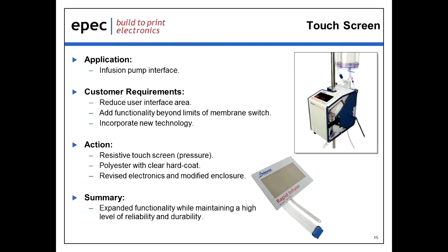The first case study we're going to review is a touch screen application. The application is for an infusion pump and also a fluid warmer. When we spoke to the customer about this, a couple of things came up as far as requirements. Number one, they wanted to reduce the size that the interface was taking up on the product itself. Secondly, they wanted to add some functionality that, using a membrane switch, they were going to be limited. And lastly, they wanted to incorporate some new technology. They wanted to modernize the interface to give the user a different experience.